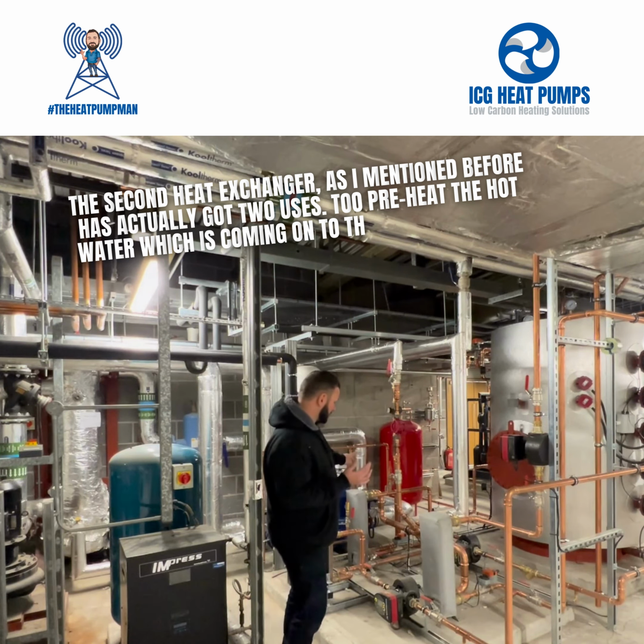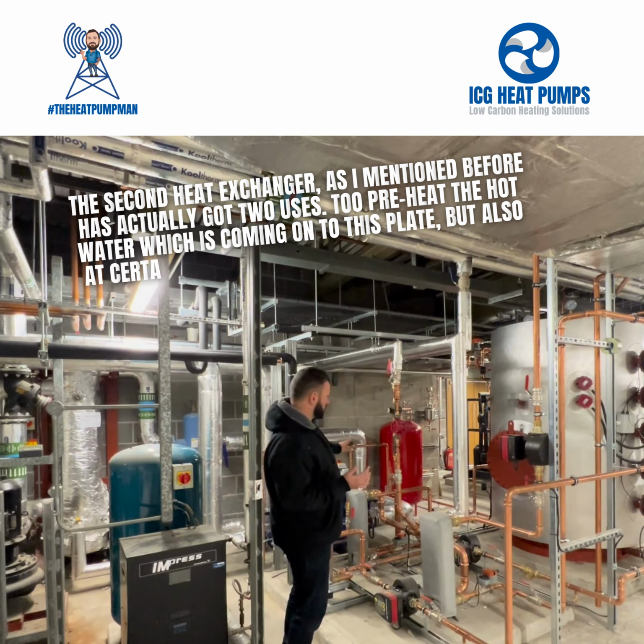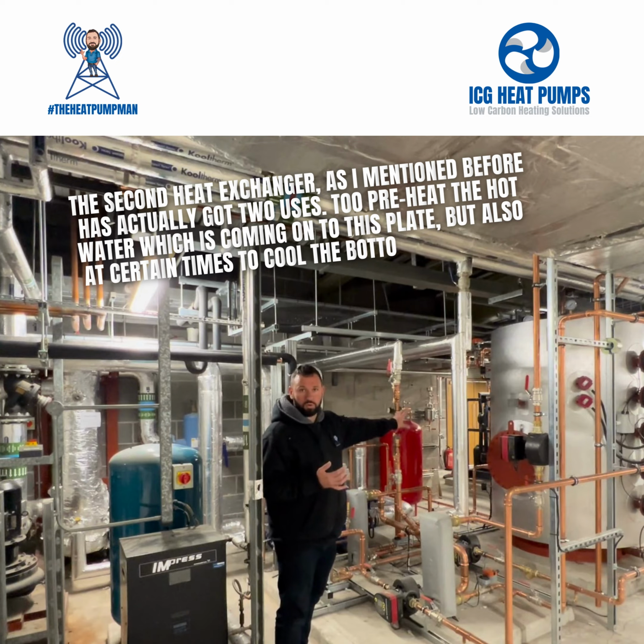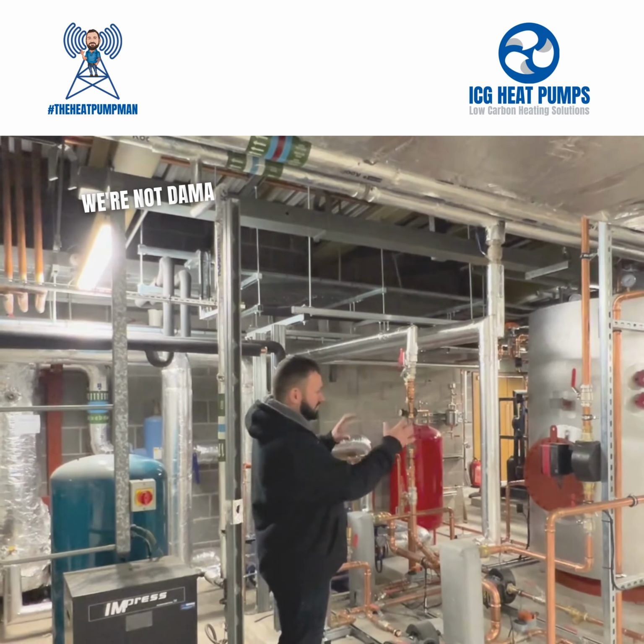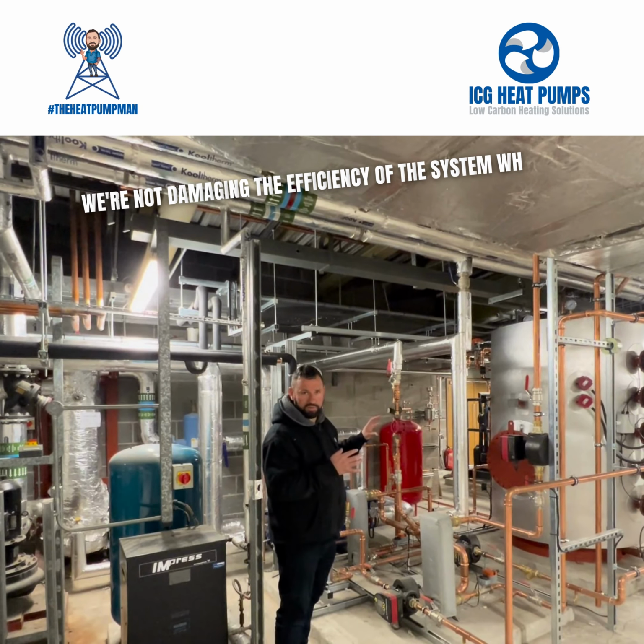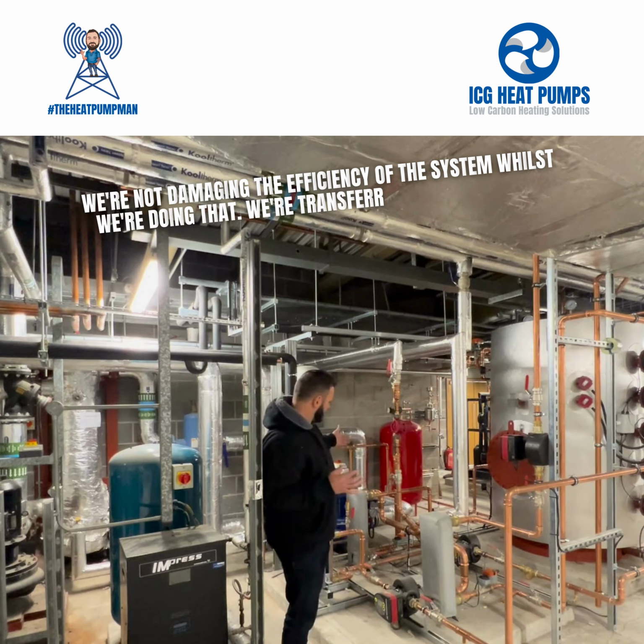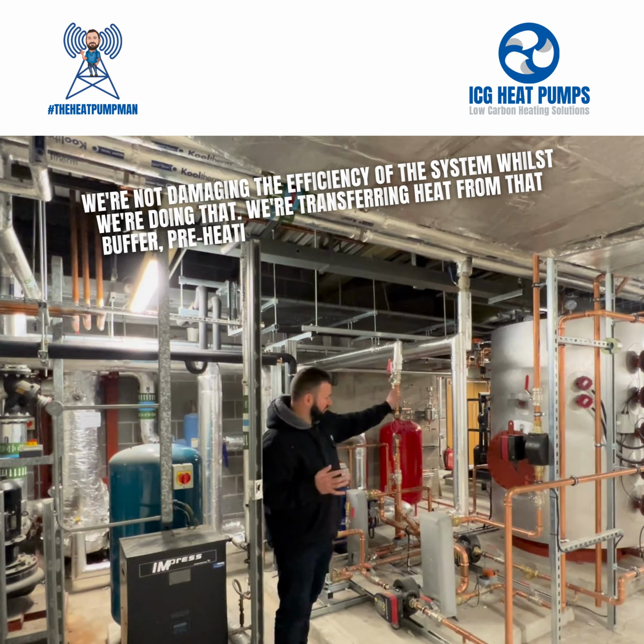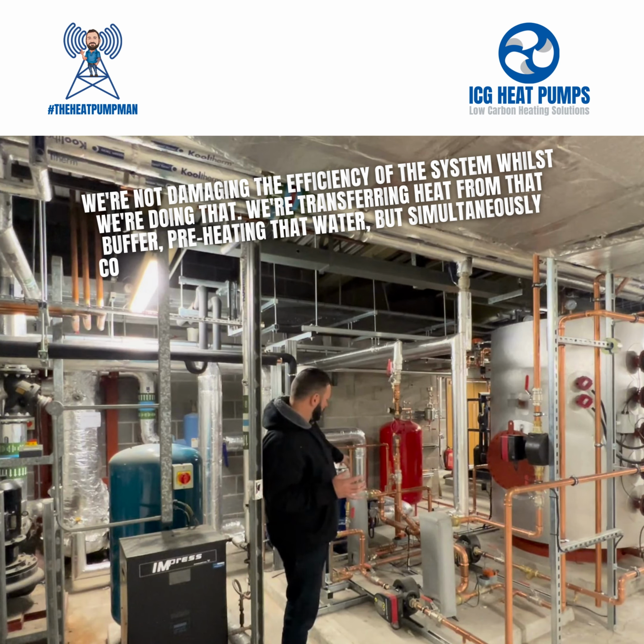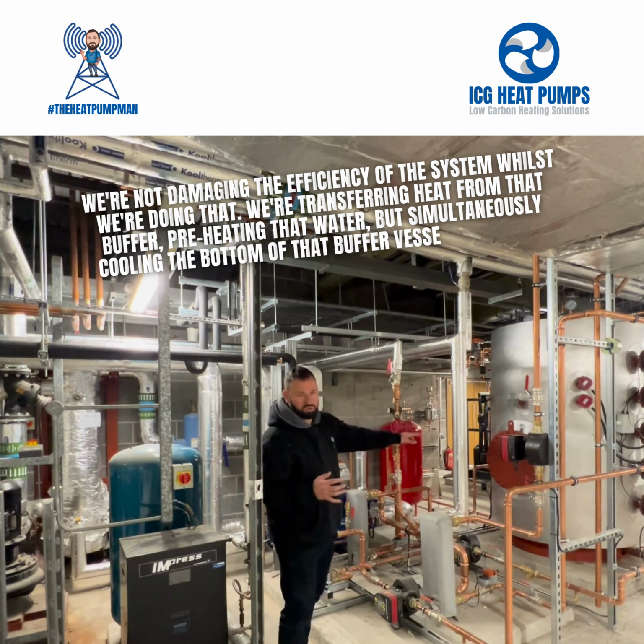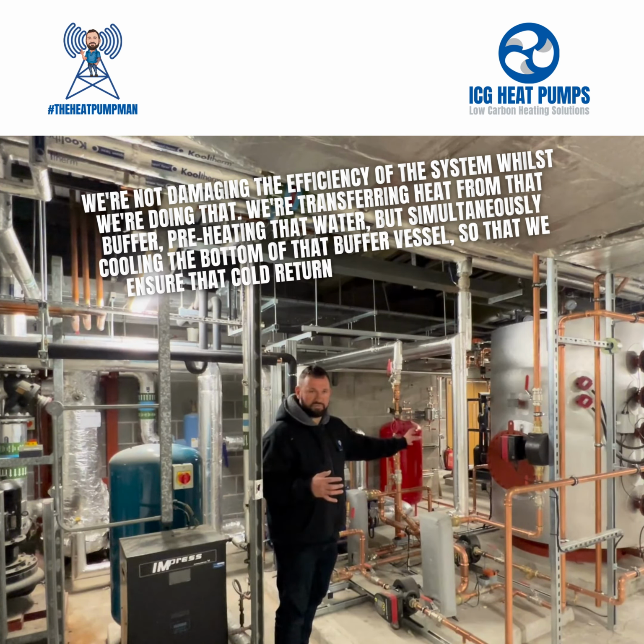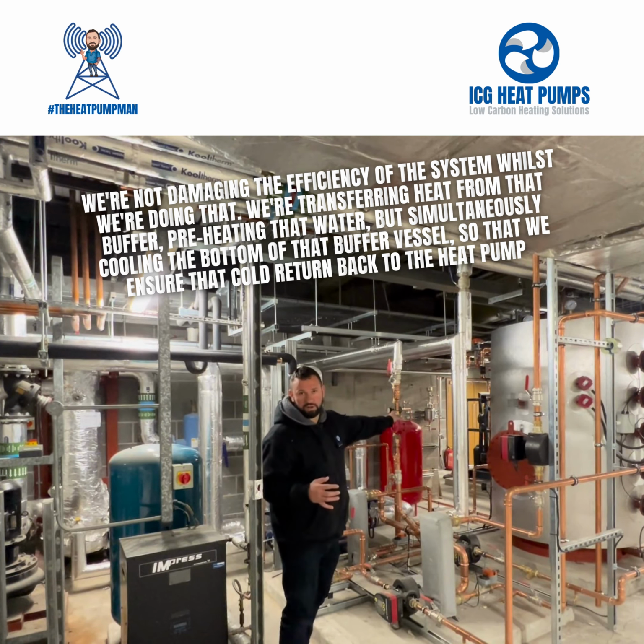the hot water which is coming onto this plate, but also at certain times to cool the bottom of the tank. We're not damaging the efficiency of the system while we're doing that. We are transferring heat from that buffer, preheating that water, but simultaneously cooling the bottom of that buffer vessel so that we ensure that cold return back to the heat pump.